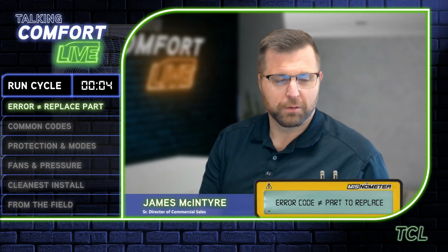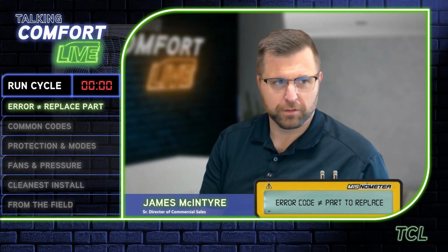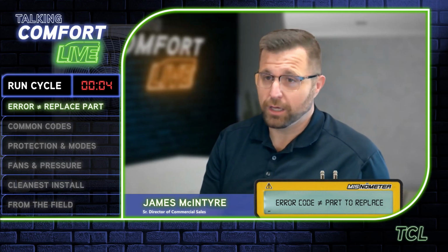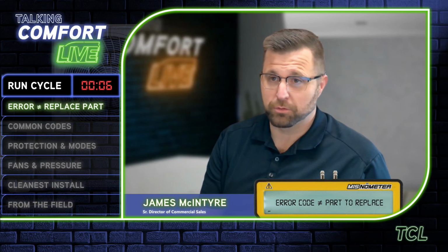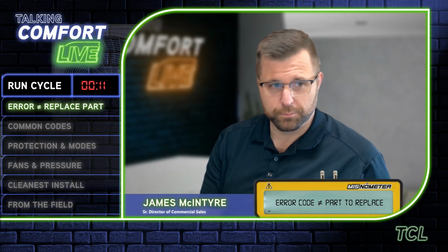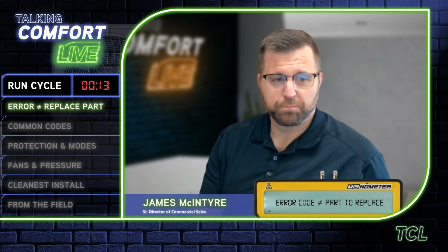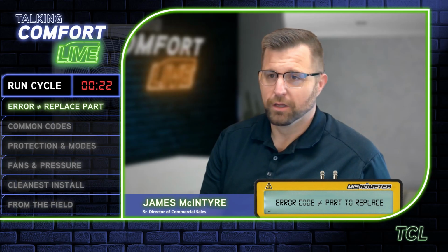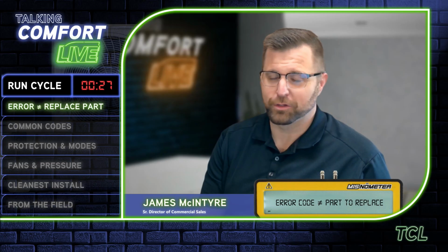Voltage is one. A lot of the mini splits out there, if you've got 230 volts hooked up, everything's good. But if you've got a 230-volt unit and you hook up 115 volts to it, you may have operation all summer long with 115 volts. Most inverter-driven equipment needs to engage the reversing valve during the heating cycle, and unfortunately, of all the things that might need both legs of power in your mini split or inverter-driven system, your reversing valve is one of those things.